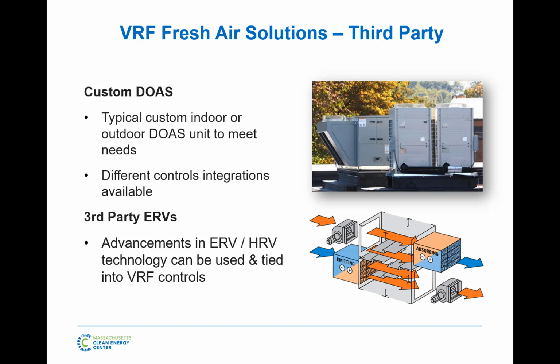The ERV technology I referred to earlier, there's a lot of evolution in that world. Even without wheels, there are ERVs that can do 90% sensible recovery. What that means is you bring in return air, supply air, and on a 0 degree day, you're going to get 65 degrees out of there for free, essentially free meaning no operational cost other than the fans. So those don't even need any trimming, because 65 is good enough to bring right to the space.